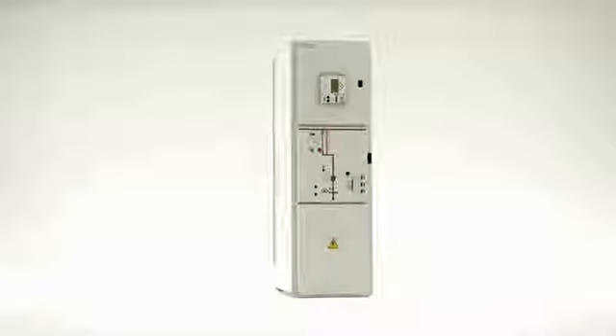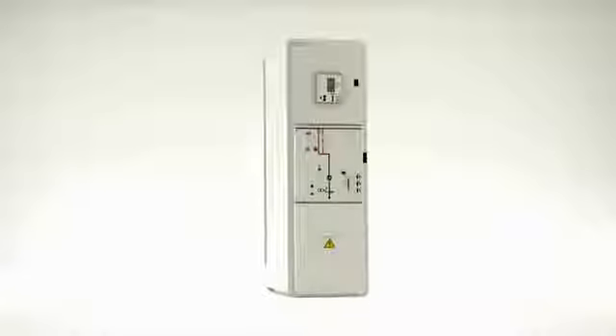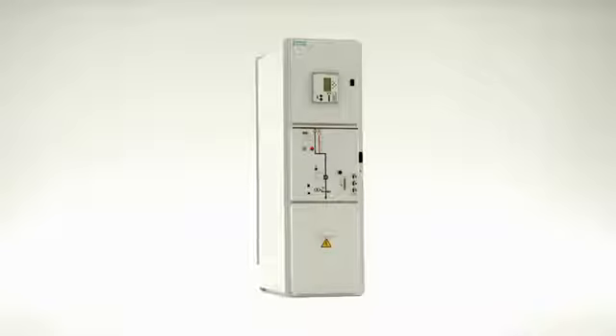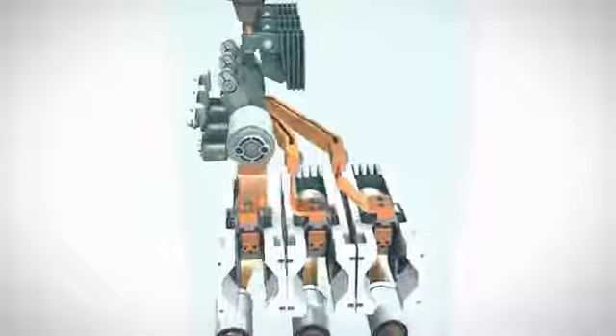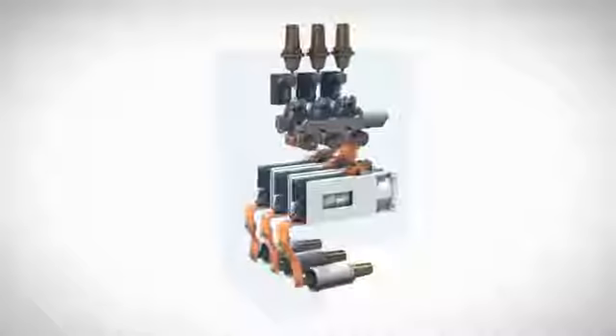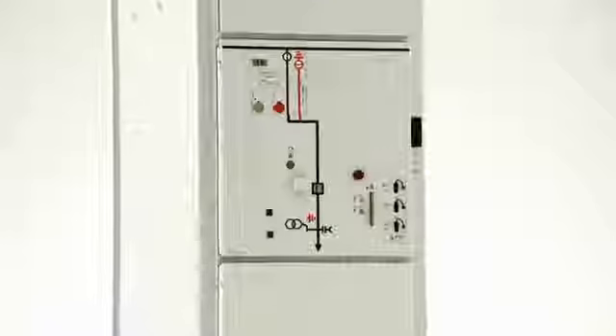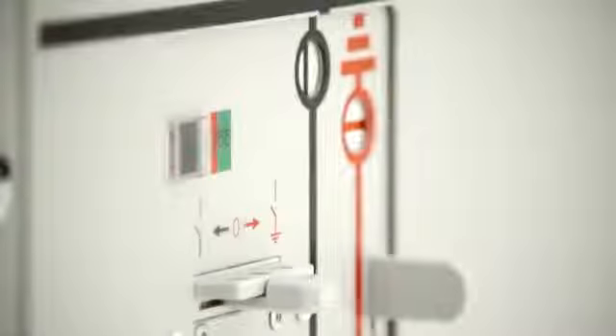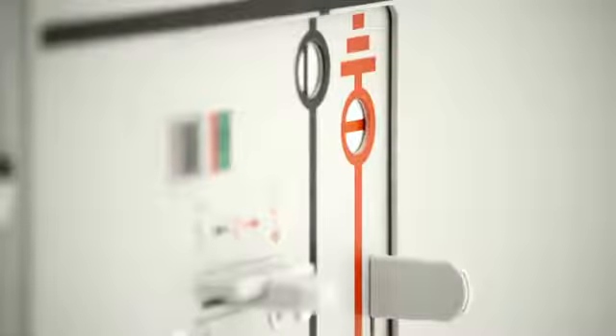Circuit breaker switchgear by Siemens is installed in the primary distribution level by customers from the power utility and industrial sector. Combined with the vacuum switching technology of the circuit breaker, the gas insulation of these switchgear assemblies provides a high level of security of operation and personal safety. Here, the choose and execute principle ensures faultless operating sequences. Choose and execute means that the three-position disconnector can generally be operated only when the circuit breaker is in the open position.